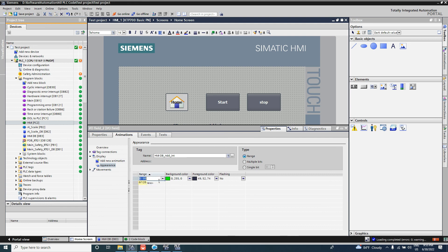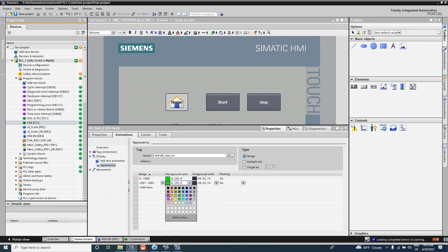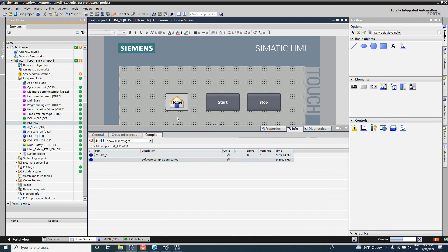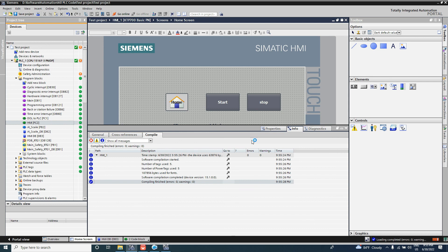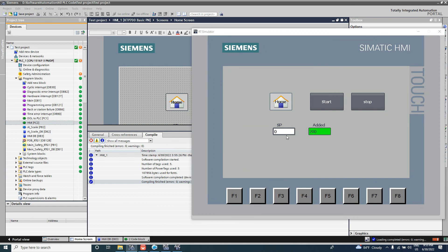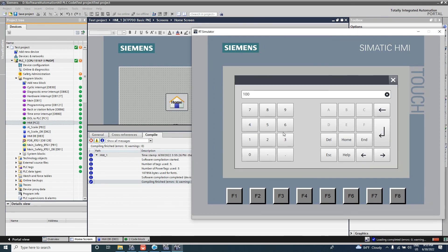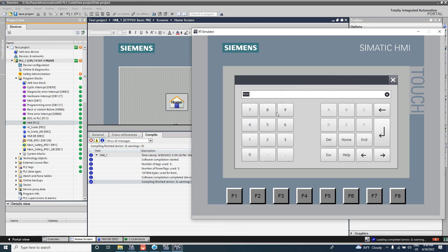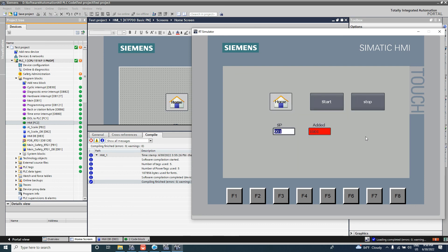If the add integer value is 0 to 1000 then the field is green; if it is 1001 to 2000 then the field is red. Simulate the HMI screen again. The value is 200 — set the setpoint to 1000, and see it is now red because 1000 plus 100 equals 1100, which is in the red range. If the setpoint is 900, the output is 1000 — green. If it is 901, the output is 1001, which should be red.